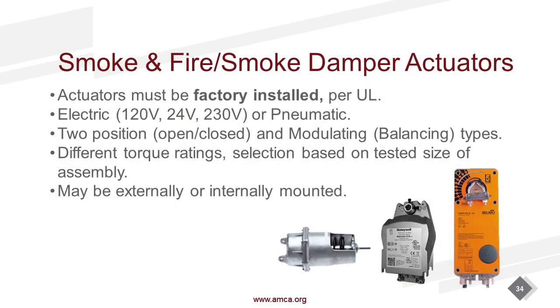Just a quick note on actuators: they must be factory installed. So your actuator and your damper are an assembly. The damper by itself is not rated. The fire smoke damper and the actuator are a combination tested and certified by UL. They give us a plan, what we call our procedure. I've got a whole set of tables that says the size of my damper, the ratings required, and what actuator I've tested and have approved.